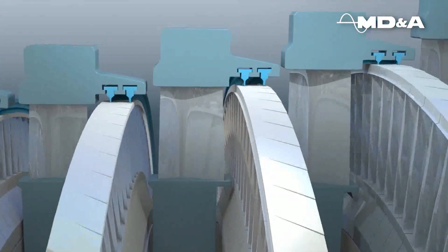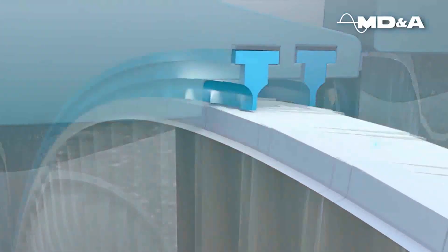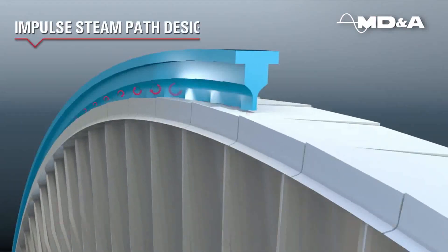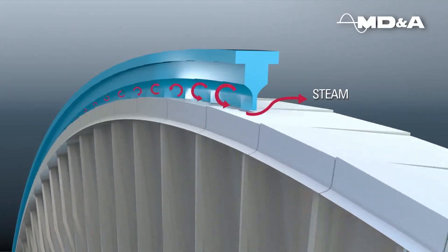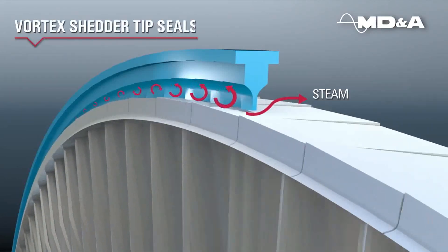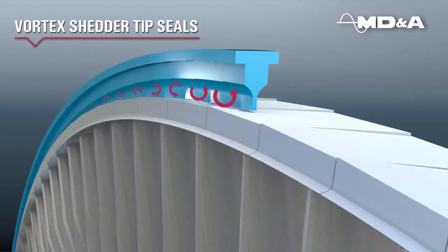In addition to packing, steam leakage occurs at the tip seals over the buckets. Whether the steam path design is impulse, reaction or a combination of both, our stainless steel vortex shedder tip seals work by creating vortices at the admission side of the seal.